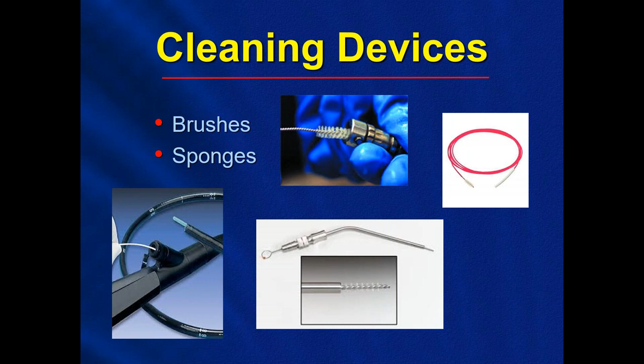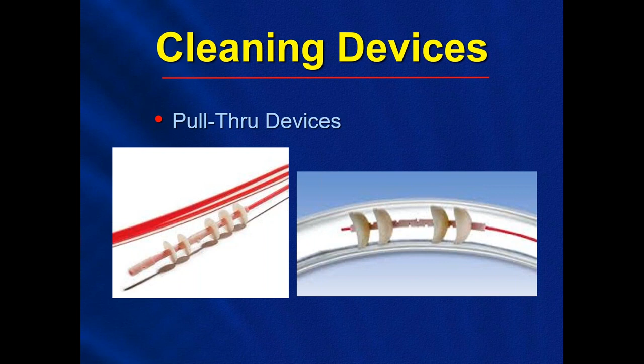Here's an example of a different technology for the cleaning of lumens and channels. It's called a pull-through device. This device, instead of being pushed through a lumen like a brush, is pulled through. You can see these silicone discs will contact the entire circular surface of the inner lumen, and pull out any bioburden that may be inside. It's kind of like a squeegee effect, like your windshield wipers, or if you were cleaning windows with a squeegee. Basically, they're rubberized discs that will pull out a lot of the debris and bioburden that may be left inside, and also help clear out some of the water that could be left in there. And they're very effective too. They did some studies on them to show their effectiveness, and compared them to brushes, and they performed very, very well compared to regular brushes.